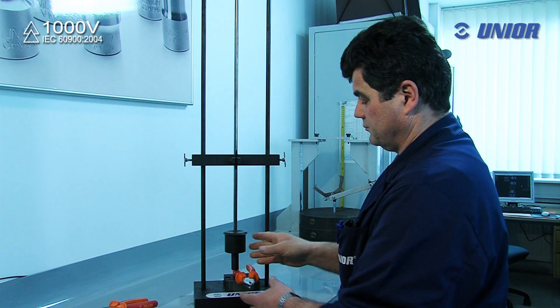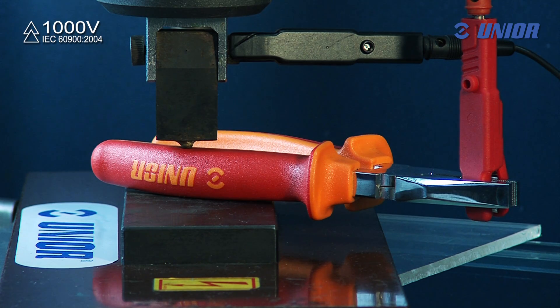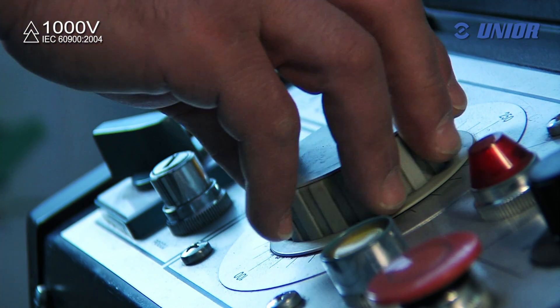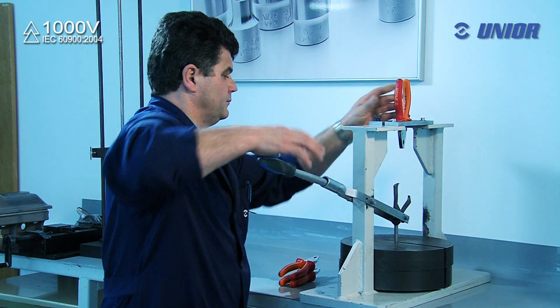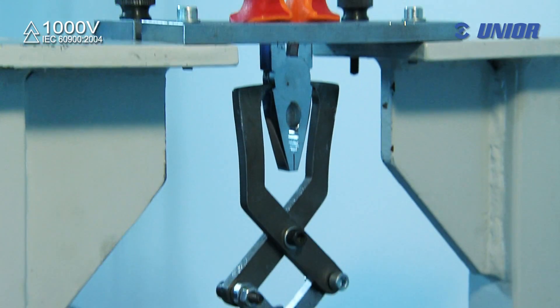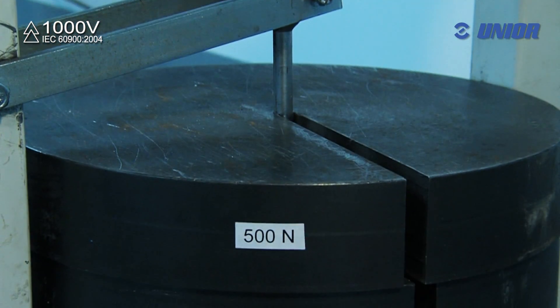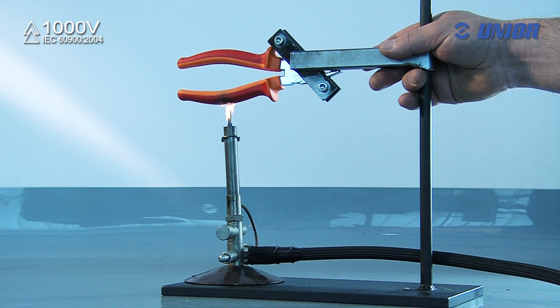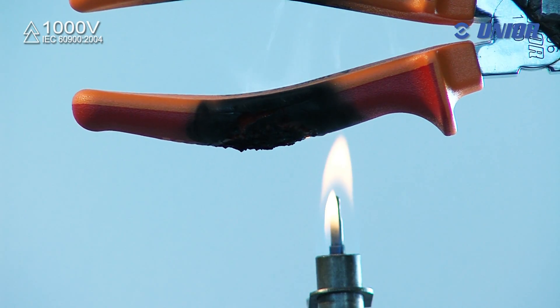Each individual item of Unior VDE tools is tested to 1000 volts. The tools must pass impact testing, insulation resistance testing, insulation coating testing, and flame extinguishing testing. The tools program has the certificate for passing the test prescribed by European standard EN 60900.